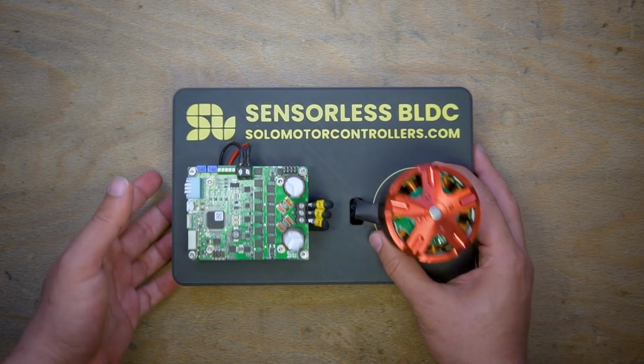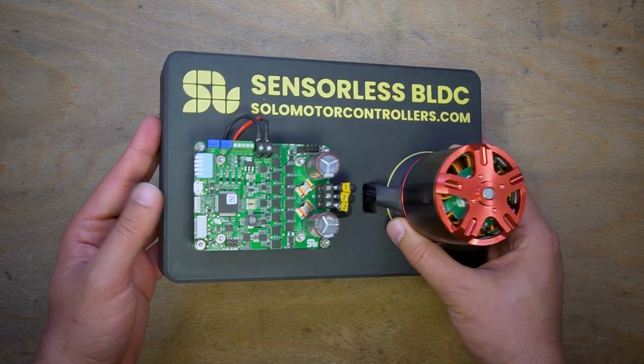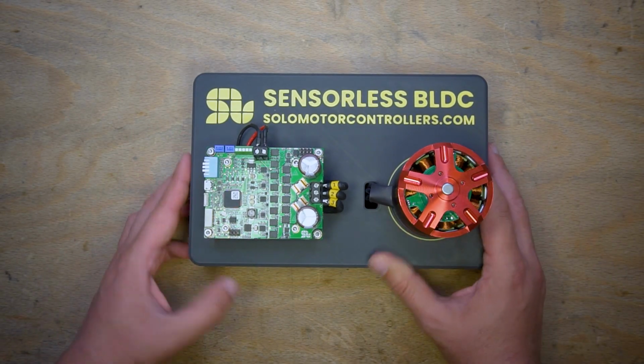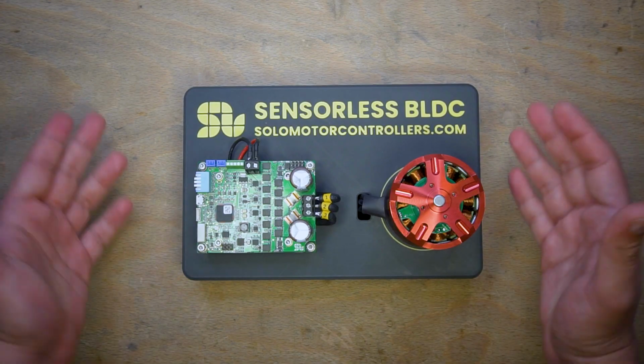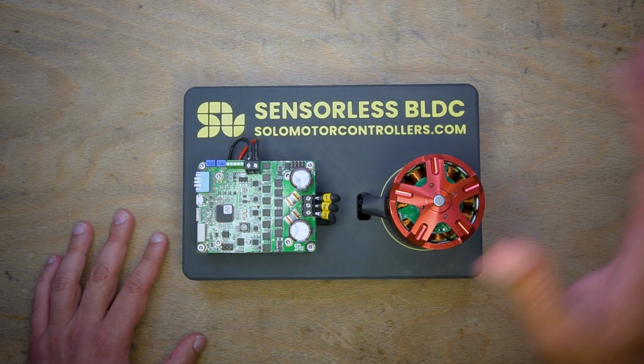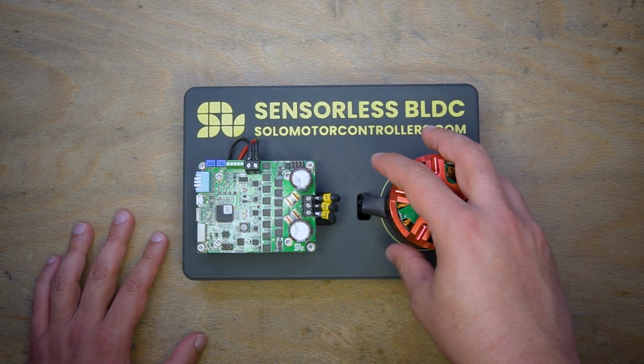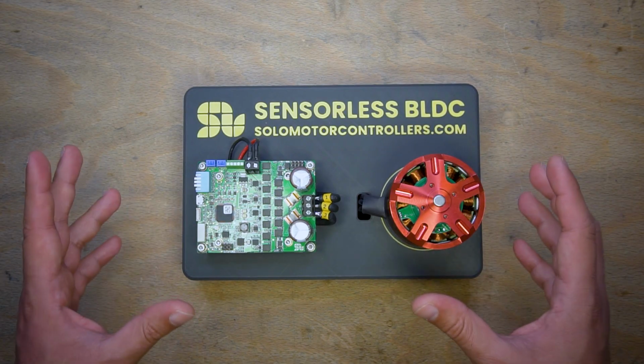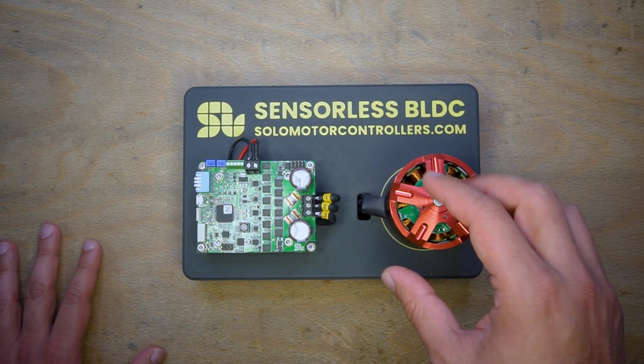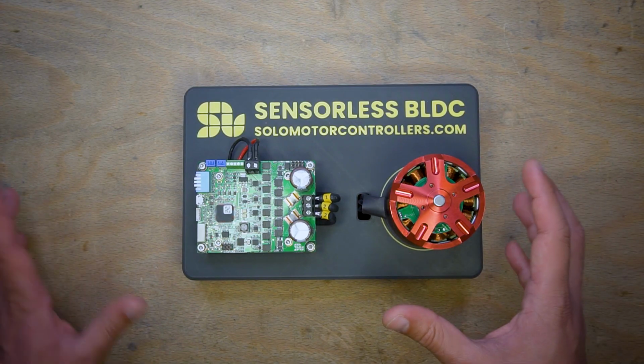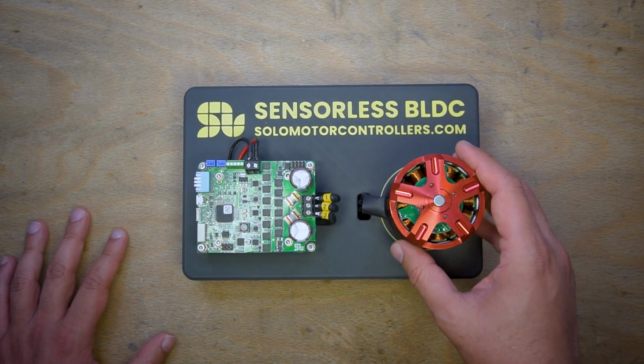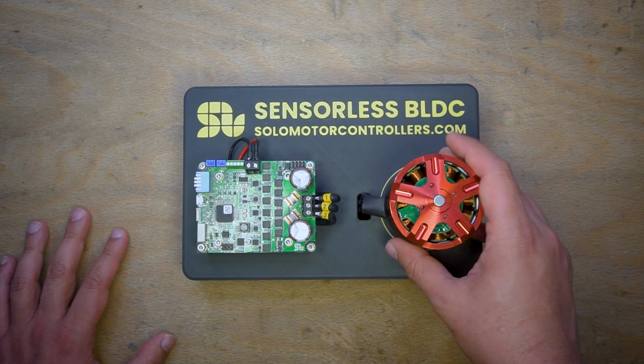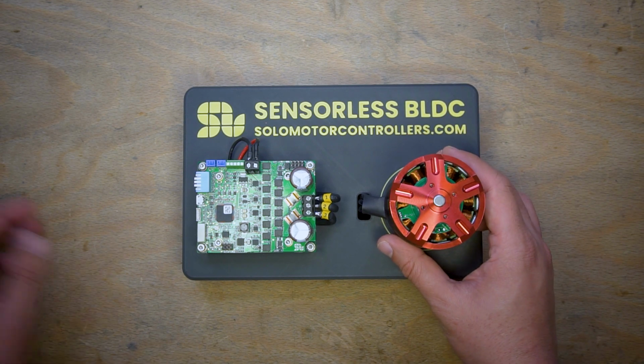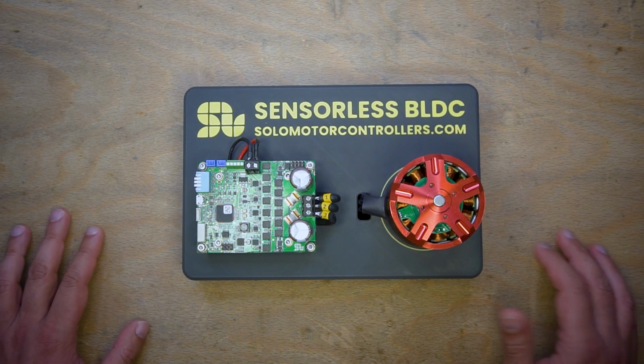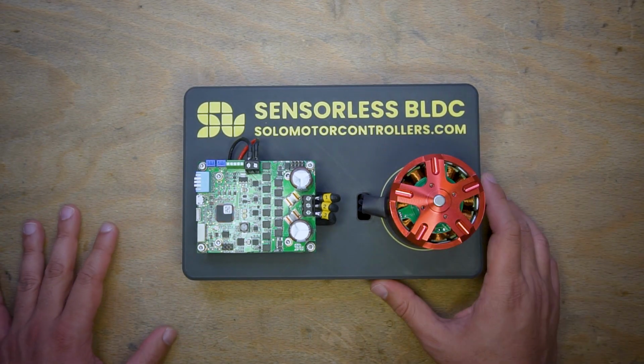The biggest difference in these kinds of algorithms is that you don't need to have any startup, and the whole algorithm is running in closed loop fashion, and it can be used for traction systems. We have two types of algorithms, but this one especially needs motors with saliency, and by that, we mean a difference between the inductance on the D and Q axis. But as a rule of thumb, usually outrunner motors like this one, BLDC motors, or internal permanent magnet synchronous motors, which are called IPMSM, do have saliency. And this algorithm is useful for those types of motors.